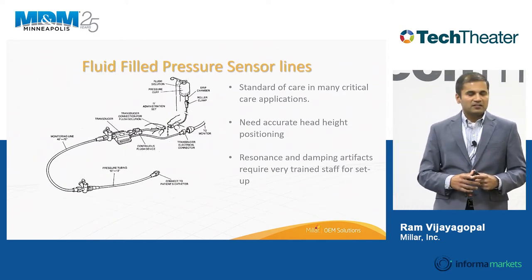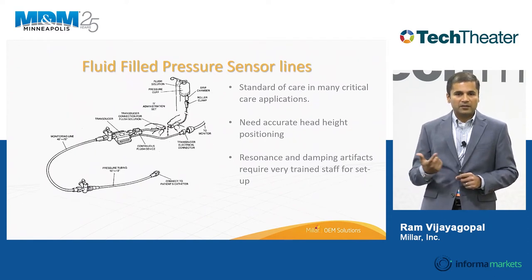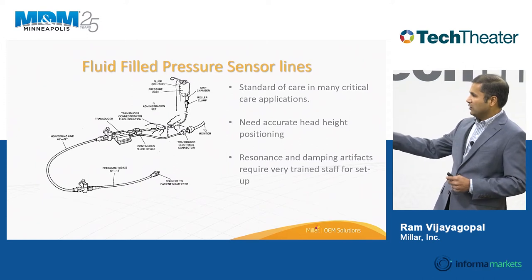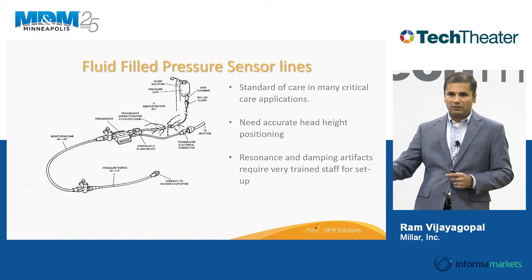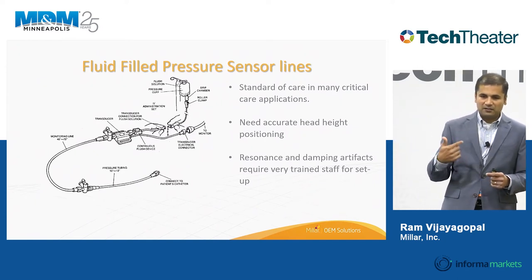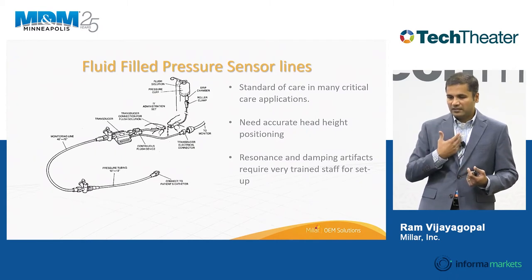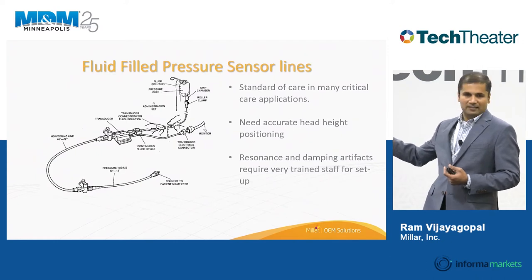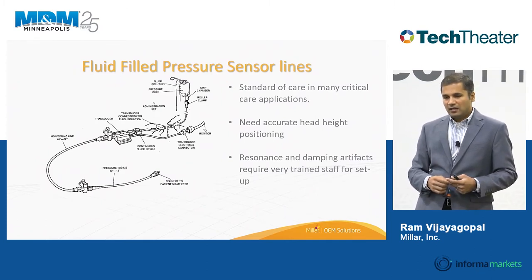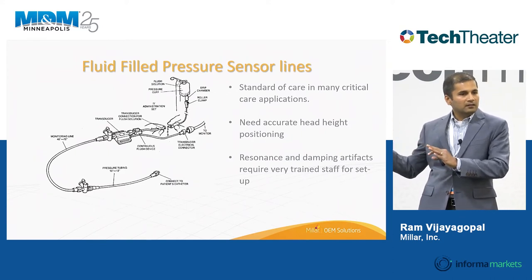Fluid-filled pressure lines are still in use in a variety of traumatic and emergency care applications — they've been in use for over five decades. In a fluid pressure line, the sensor is located outside the body, and a saline-filled tube runs from it to a catheter inserted into the vasculature. Pressure is communicated from inside the body through this fluid to the sensor. These lines suffer from challenges like resonance and damping, require a lot of expertise to set up, but are still a standard of care in many critical care applications today.